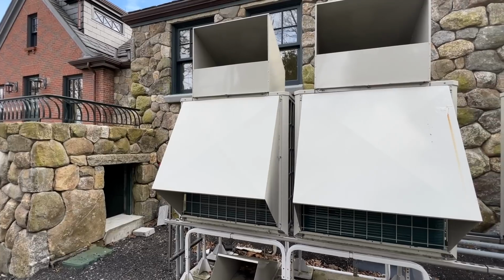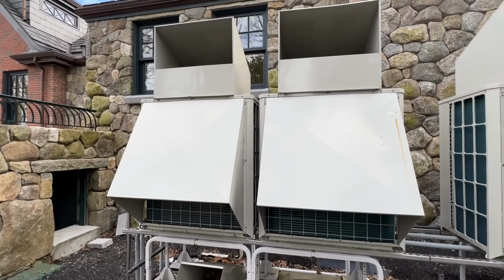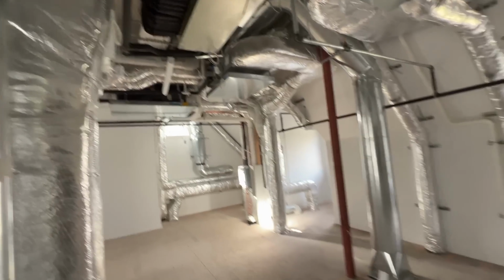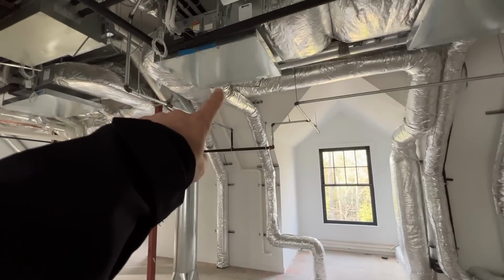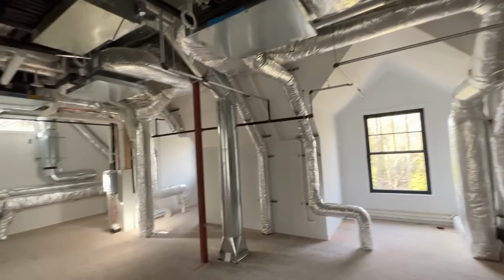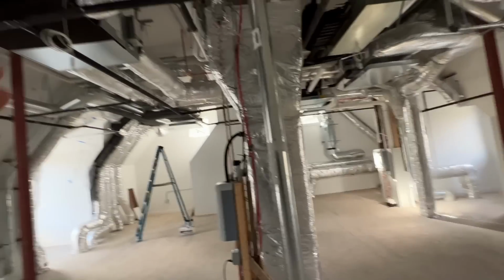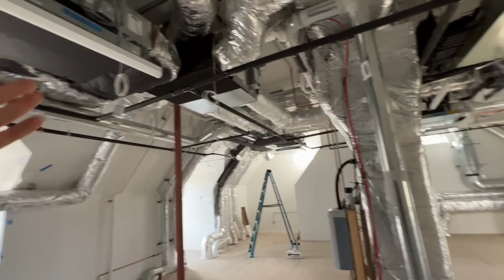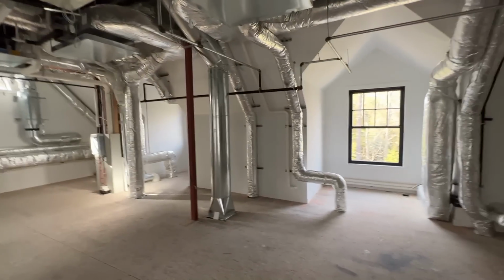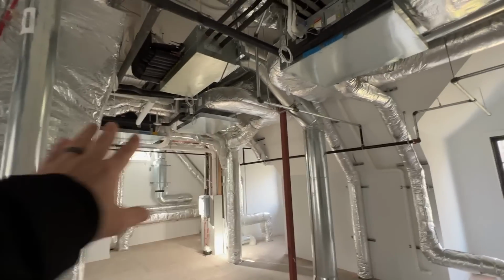What's really interesting about this system, which is more of a commercial design, is that it can heat and cool differentially. So this unit going to, say, the master bedroom could be on cooling mode, while the baby's room over here could be on heating mode, and the system is smart enough to run both at the same time, very efficiently.